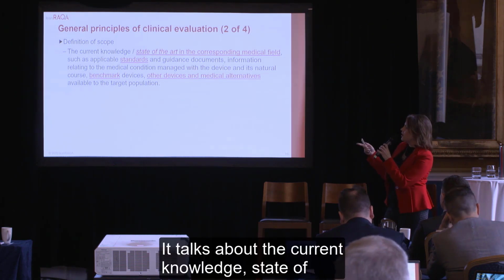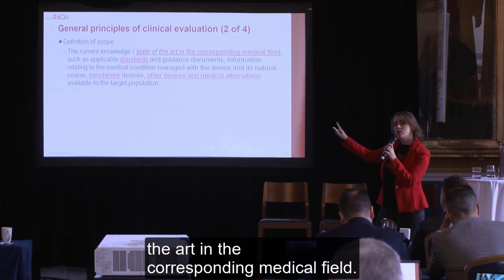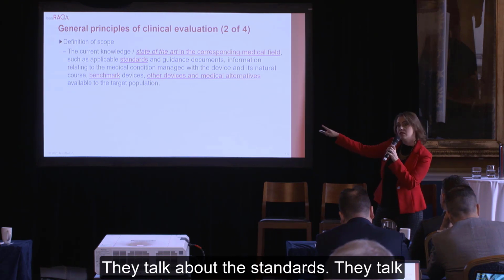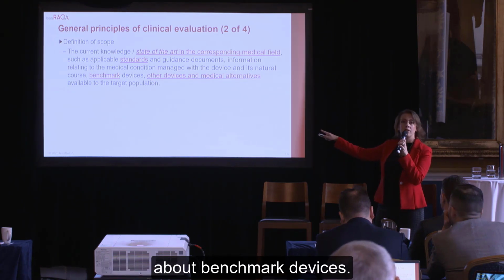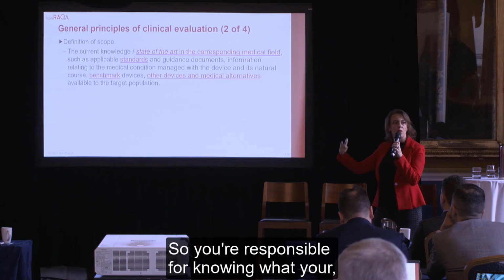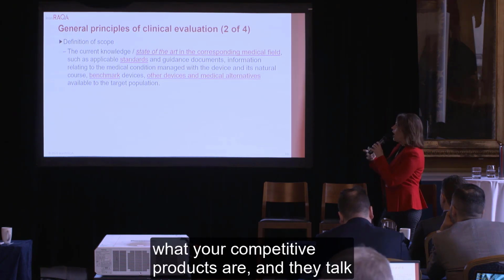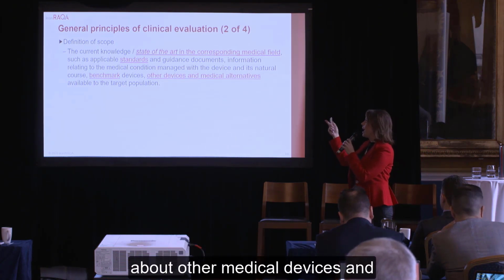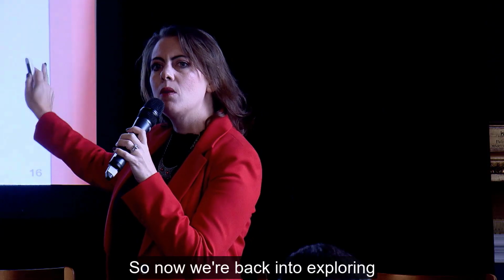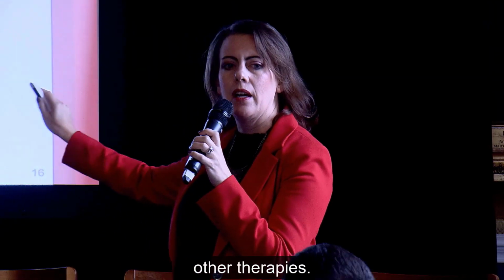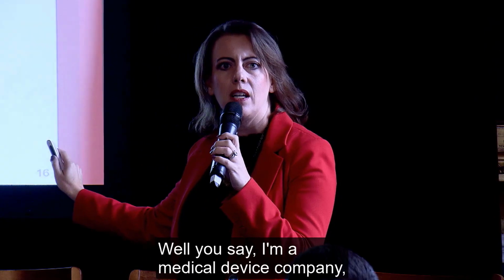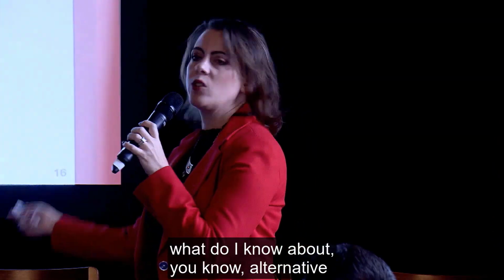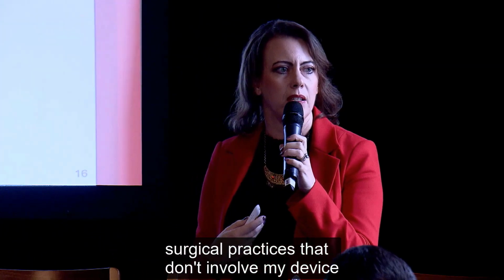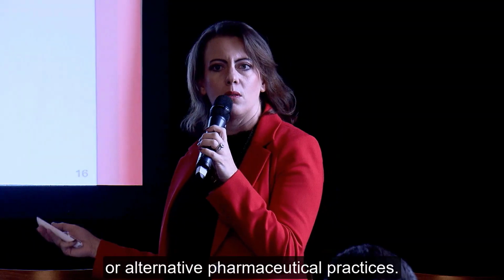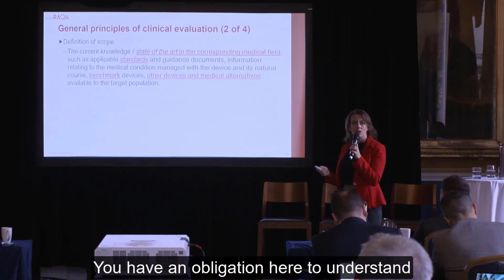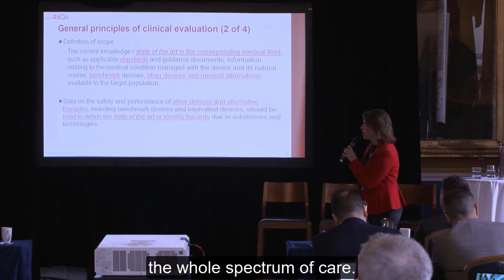It talks about the current knowledge, state of the art in the corresponding medical field. They talk about the standards. They talk about benchmark devices, so you're responsible for knowing what your competitive products are. And they talk about, again, other medical devices and medical alternatives. So now we're back into exploring other therapies. Well, you say, I'm a medical device company. What do I know about alternative surgical practices that don't involve my device, or alternative pharmaceutical practices? You have an obligation here to understand that whole spectrum of care.